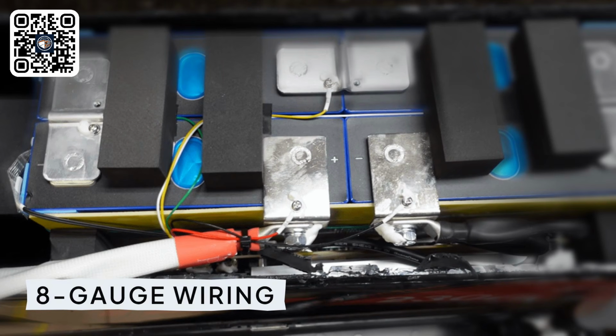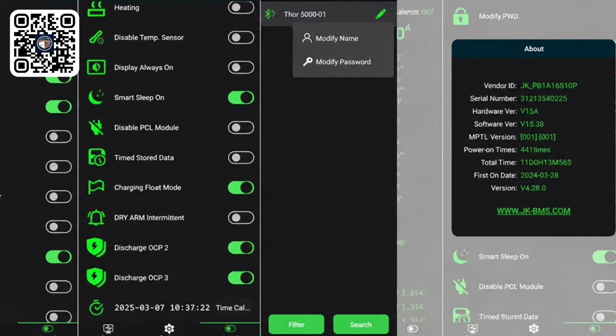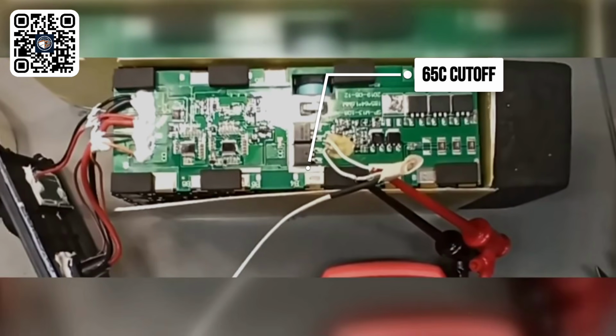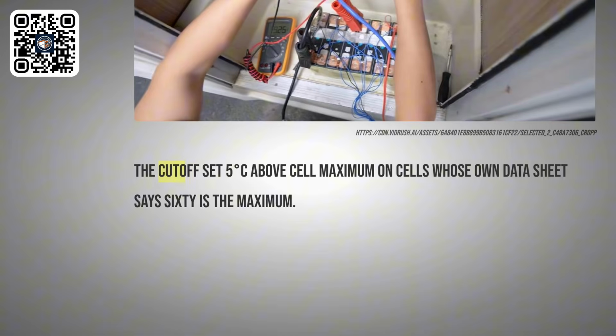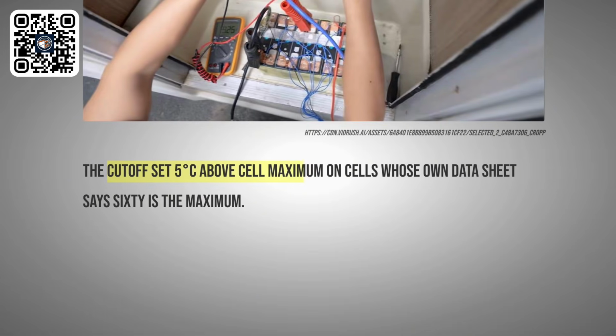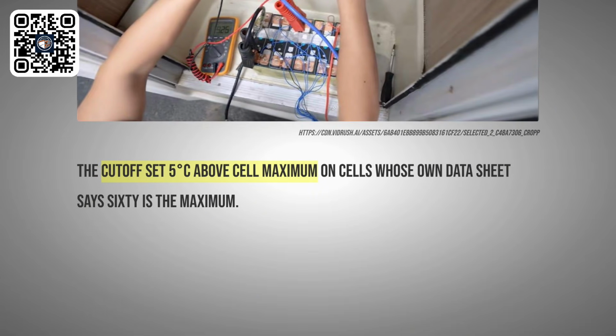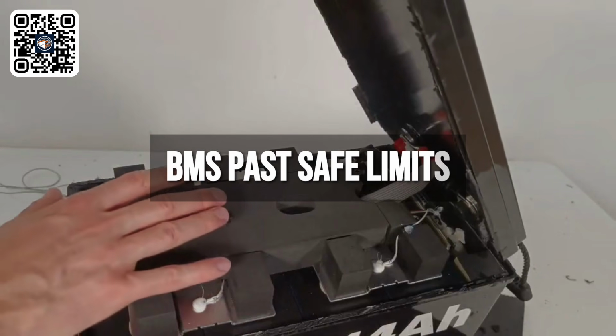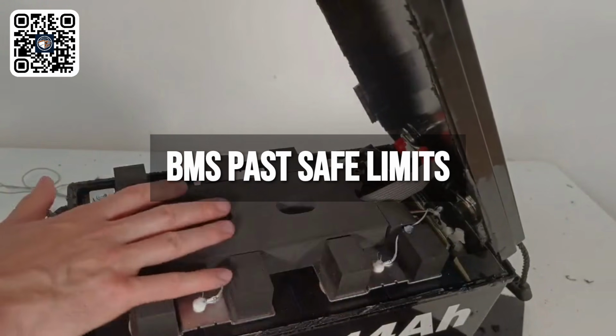The internal terminal wiring was 2 runs of 8 gauge. The overcurrent protection shipped set to 300 amps by default, and the discharge over temperature cutoff was set at 65 degrees Celsius on cells whose own datasheet says 60 is the maximum. Read that one twice. The safety device was configured past the safe limit of the thing it was protecting.